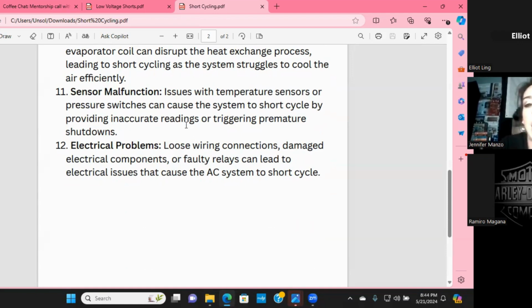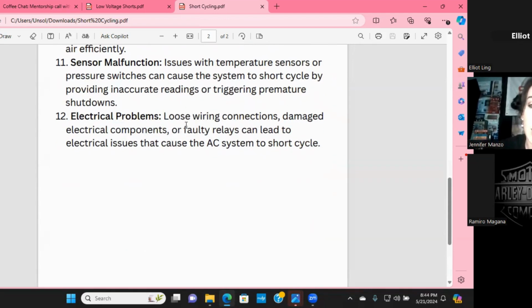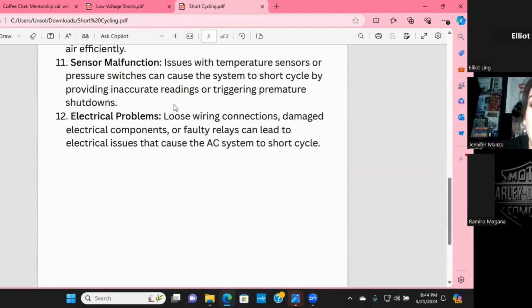If you have something happening that doesn't seem quite right to you, check your pressure sensors. Always check high pressure and low pressure sensors. And if it's on a furnace or something like that, check your flame sensor. Sensors are a problem. And then electrical problems, we talked about loose wiring. Lots of things like that can cause it as well. So that one's on the short cycling issue. Has anybody here seen any of these reasons in real life, out in the field?